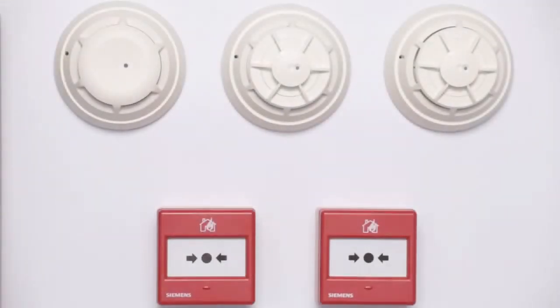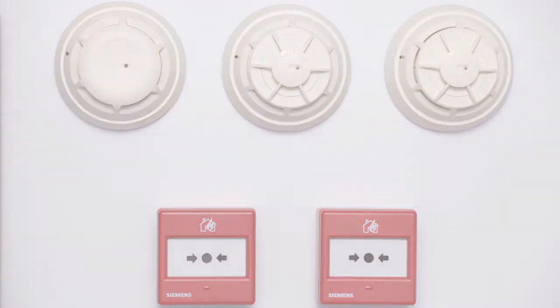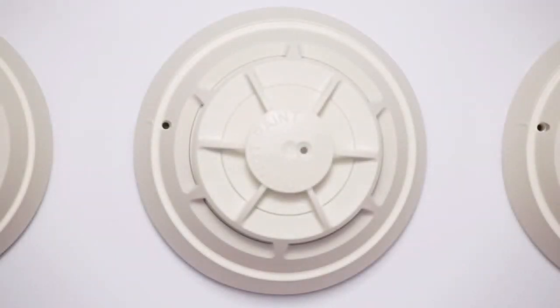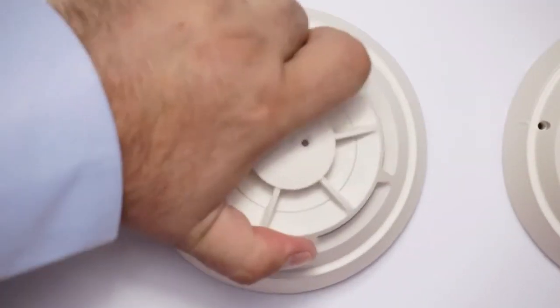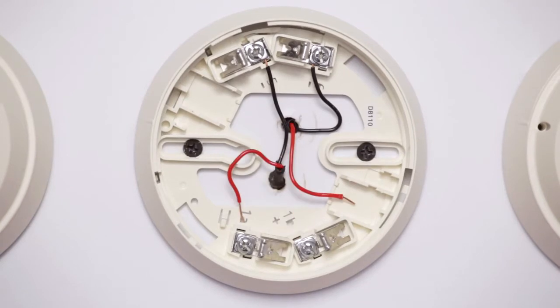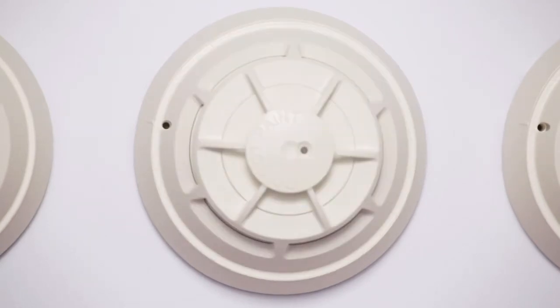Test mode is also automatically enabled if you connect the line on the panel. This is indicated by a green blinking LED on the detector. This test mode is automatically deactivated after approximately 30 minutes. Furthermore, you can easily find a wiring mistake. If a detector is not blinking, the wire between the previous element and the detector is not connected properly.